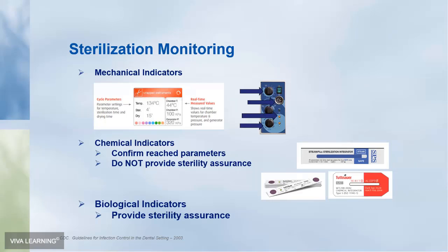It doesn't say how long it was there necessarily. So you need to look at the mechanical indicator, whether it's digital or analog. The digital are certainly more sophisticated, and you can get printouts of them or load them onto a USB port and then archive them that way. The chemical indicators, as I've mentioned, confirm that the sterilizer reached the parameters. It does not provide sterility assurance in any way, shape, or form. It does confirm that it reached the parameters, that's all.